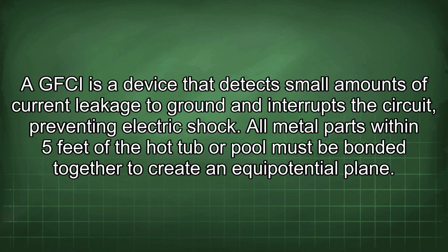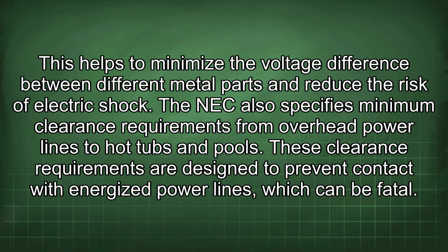GFCI protection is required for all electrical circuits serving a hot tub or pool. A GFCI is a device that detects small amounts of current leakage to ground and interrupts the circuit, preventing electric shock. All metal parts within 5 feet of the hot tub or pool must be bonded together to create an equipotential plane. This helps to minimize the voltage difference between different metal parts and reduce the risk of electric shock. The NEC also specifies minimum clearance requirements from overhead power lines to hot tubs and pools. These clearance requirements are designed to prevent contact with energized power lines, which can be fatal.